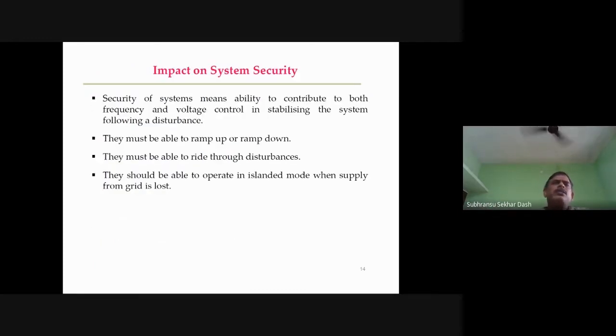Then impact on power system stability, that is, you talk about transmission planning. The first point is impact on system security. What happens to system security when a wind farm is connected to a grid? Security of the system means the ability to contribute to both frequency and voltage control in stabilizing the system following a disturbance. When a disturbance is there, what does system security mean? See, when you synchronize a grid to the wind farms, as per the synchronization rule, voltage and frequency should be matched. But due to change in speed, there is a possibility that voltage and frequency may not match. So it may affect the system security. They must be able to ramp up or ramp down. They must be able to ride through disturbances. They should be able to operate in island mode when supply from the grid is lost.